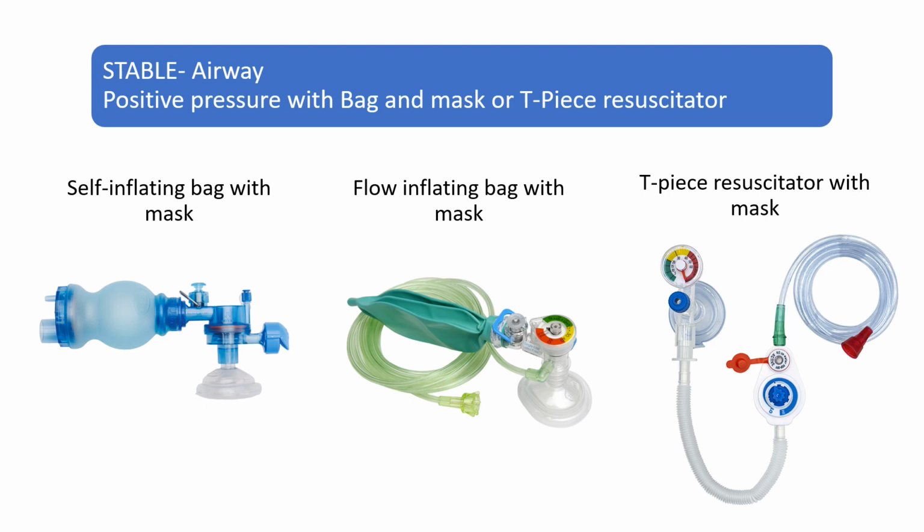We don't typically use those in the field, but it just connects right up, and you can provide PEEP with it, and you just push this little button down, and it provides a jet or push of air in there up to a certain pressure. Flow inflating bag. These are seen a lot. These are fantastic for this.